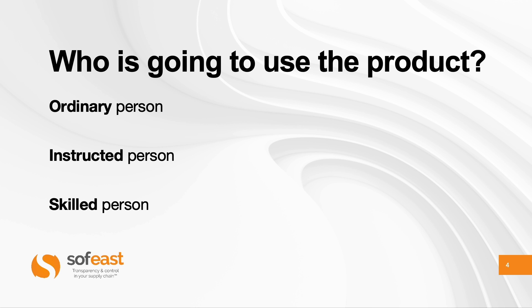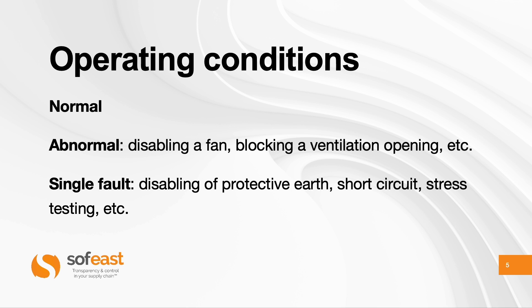Operating conditions is another very important concept. Normal operating condition is the way the product is supposed to run most of the time. An abnormal condition is, for example, a fan being disabled so it cannot cool the product as intended — the product might overheat, but there still might not be any hazard. From the point of view of this IEC standard, this would be no problem as long as the product overall remains safe. Blocking a vent, for example, falls under this category.